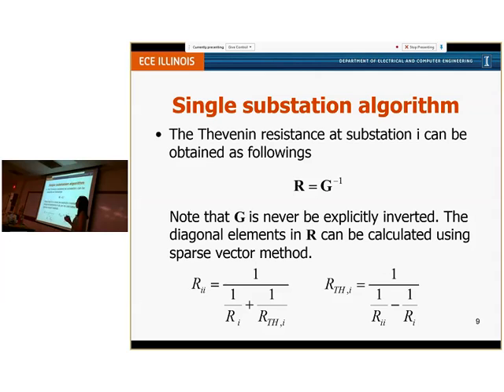So we need to know the Thevenin equivalent resistance. Then we can get it from the driving point resistance. Driving point resistance is the diagonal element of the resistance matrix, and the resistance matrix is the inverse of the conductance matrix G. But note that G should never be explicitly inverted, because in a large system, G is usually a sparse matrix, and we can find the diagonal elements of the inverse of the sparse matrix using the sparse matrix sparse vector method. Then here we got the equation for the Thevenin equivalent resistance at substation I.